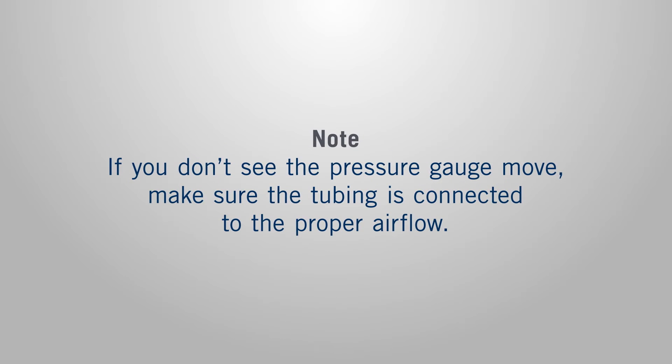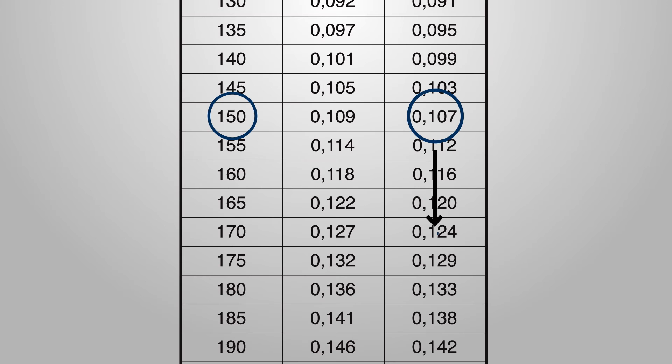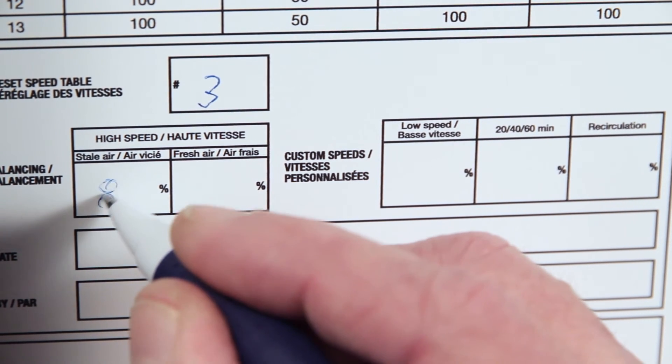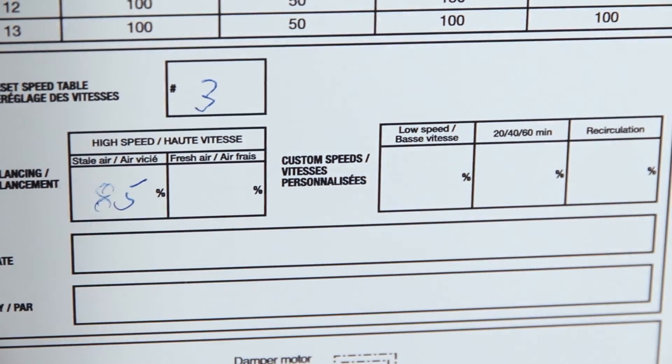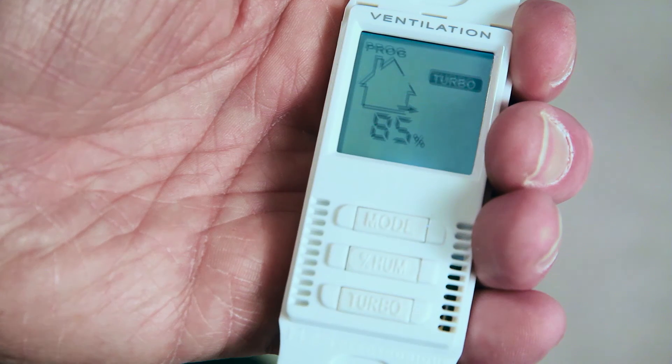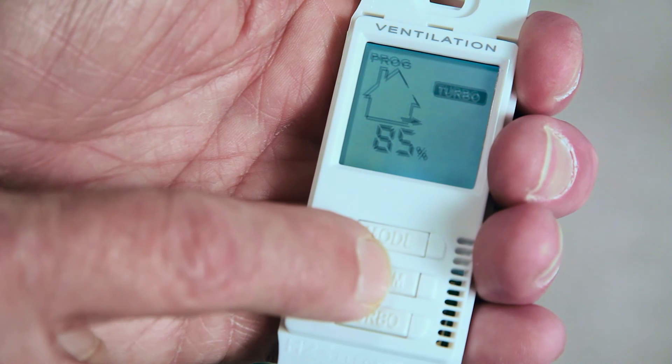If you don't see the pressure gauge move, make sure the tubing is connected to the proper airflow. Check the pressure gauge along with the unit balancing chart until the desired airflow is reached. Take note of the setting value at this step, as it will disappear by pressing the accept button. Press the middle button to accept the chosen percentage.